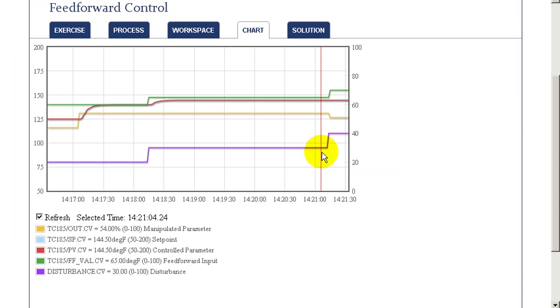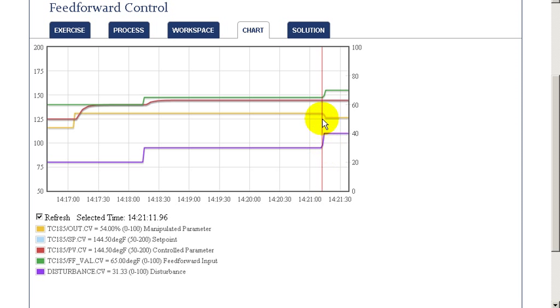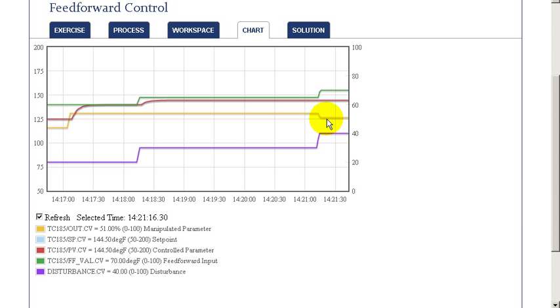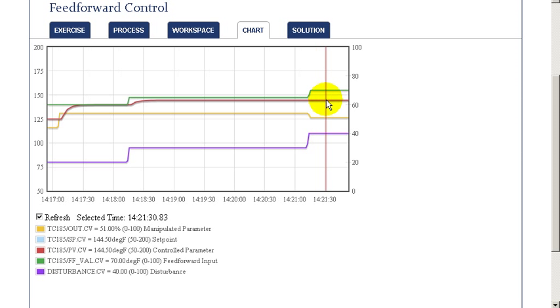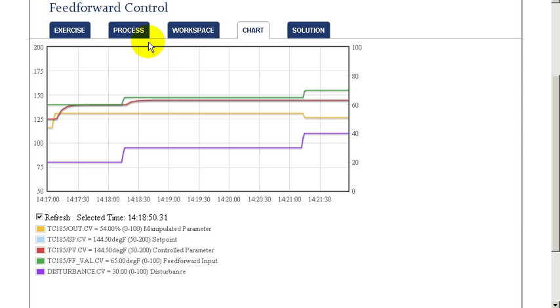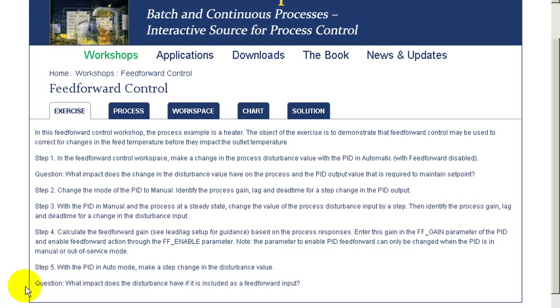This is better seen by looking at our chart. As we can see, when the disturbance changed by step, the output of our controller also changed immediately. As a result, there was no change in the outlet temperature. We've been able to eliminate the disturbance impacting our outlet temperature through the use of feedforward, by having the correct gain and setup. We hope this exercise has been helpful in better understanding the way feedforward is commissioned and its benefit in terms of minimizing the impact of a measured disturbance on the control loop.